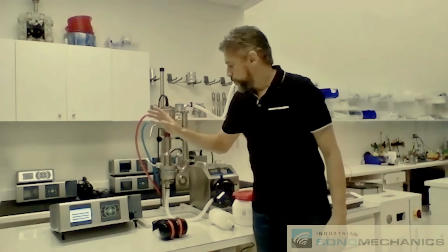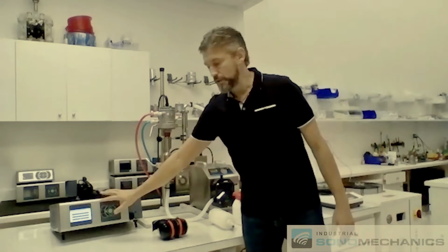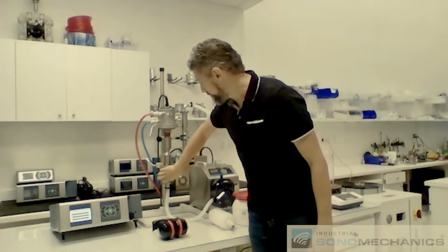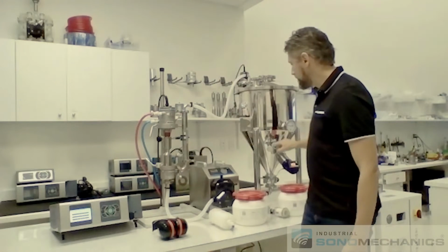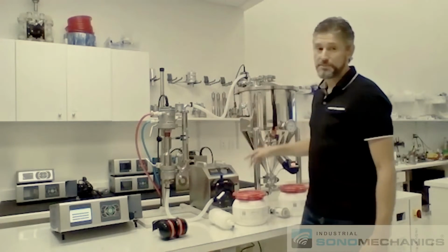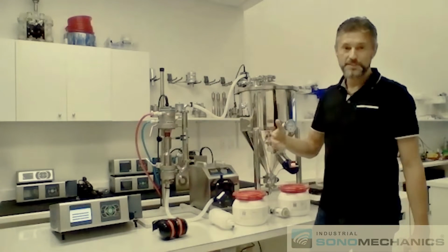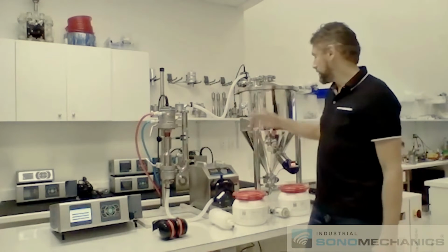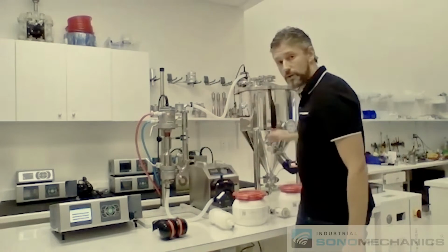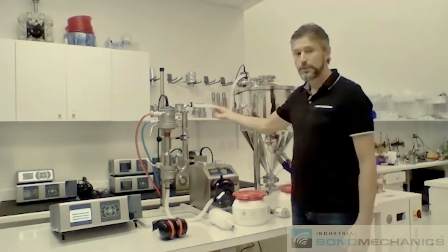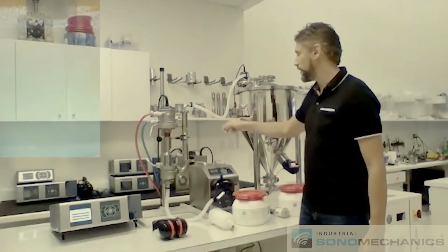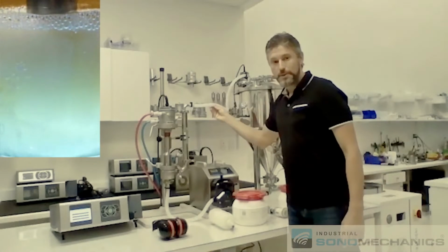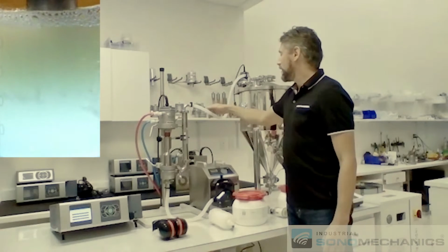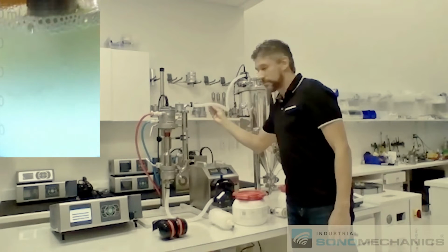So once the liquid is flowing and you have your ultrasound on, there is going to be cavitation in this chamber, and you're taking the premix, which progressively becomes the nanoemulsion as the time passes. So the liquid will be going around, and you can watch it through this hose, or you can incorporate sight glass if you desire, and watch the liquid become progressively more and more translucent. When the process is done, you should be able to see light through this. You should be able to read text through it.